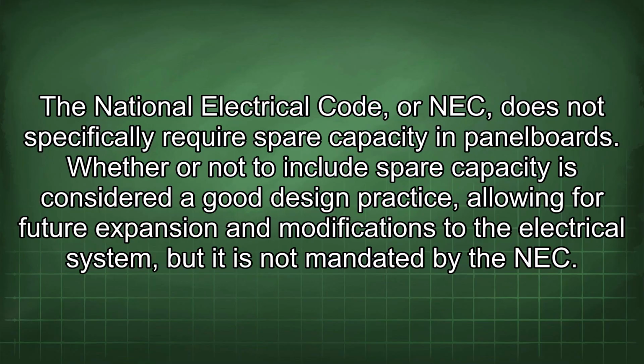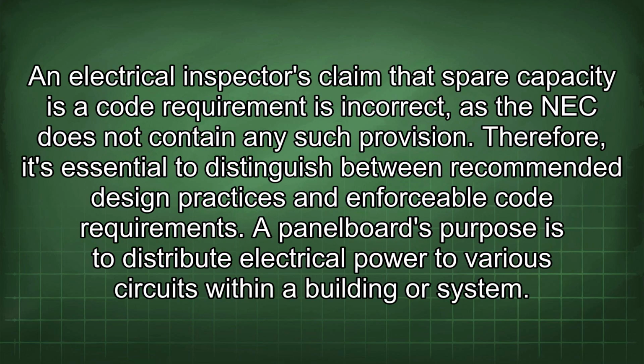The National Electrical Code, or NEC, does not specifically require spare capacity in panel boards. Whether or not to include spare capacity is considered a good design practice, allowing for future expansion and modifications to the electrical system, but it is not mandated by the NEC. An electrical inspector's claim that spare capacity is a code requirement is incorrect, as the NEC does not contain any such provision. Therefore, it's essential to distinguish between recommended design practices and enforceable code requirements.